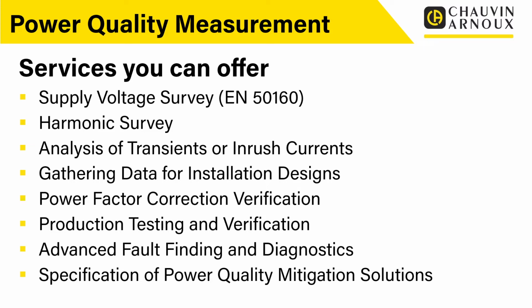Because they work like a real-time multimeter, but for power quality. You can see those traces on the screen, actually do the measurements in real time and see what that does to your harmonics or your power factor or whatever's going on. So that's really where these power quality analyzers with the big color displays really come into their own for doing this fault finding and diagnostic work.